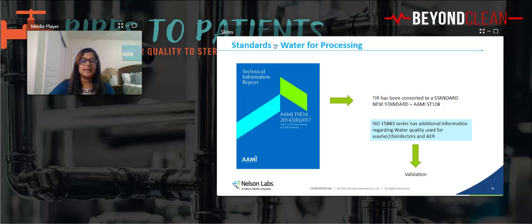Now, standards for processing. I'm sure you've seen this one, AAMI TIR34. TIR has been converted to a standard, to a new standard. Now, ISO 15883, I'm sure some of you have heard about it, but some of you may not have. It's a series, but the water quality used for AERs is in that standard. Part 6 is what you want to look at. They have a huge section on AERs in the back that talks about what kind of water quality systems they need and how they will be measured for a validation. And we do validate that water system. When we do self-disinfection validations, we're also looking at the water quality for it.